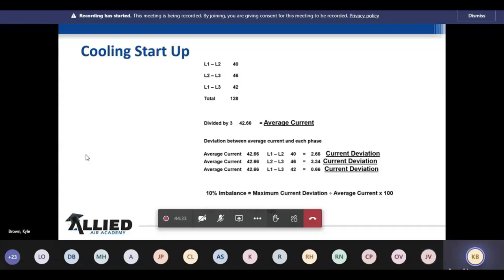The very last one, 0.66, but you'll notice on the current, it's a lot more forgiving on the imbalance than the voltage is on the imbalance. So we got a 10% maximum imbalance on this. So the 7.82, we are well within the imbalance. That doesn't mean we can't go ahead and take a look. And if we've loaded up 2 of the legs with single phase stuff, like outdoor fan motors, if this unit's had outdoor fan motors changed out on it quite a bit, you may, and we talk about startups, but if you go on down the road in the lifetime of this unit, and you get a technician that doesn't realize that they have to keep these loads balanced on these 3 legs, they may start blowing fuses for no reason.